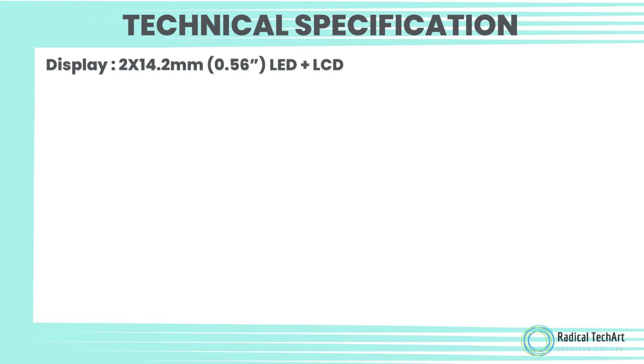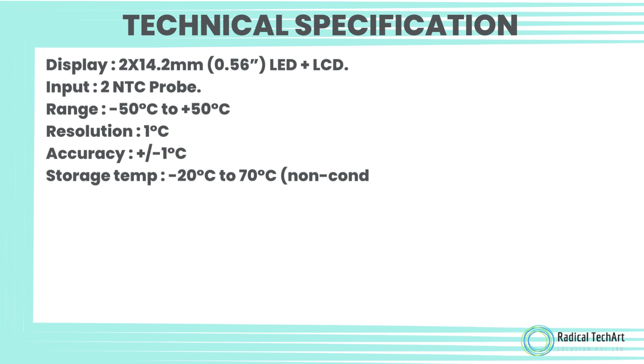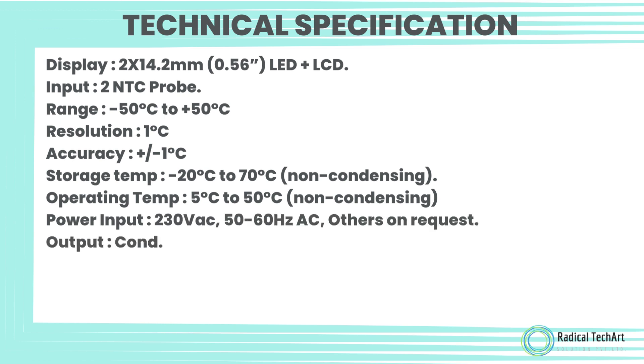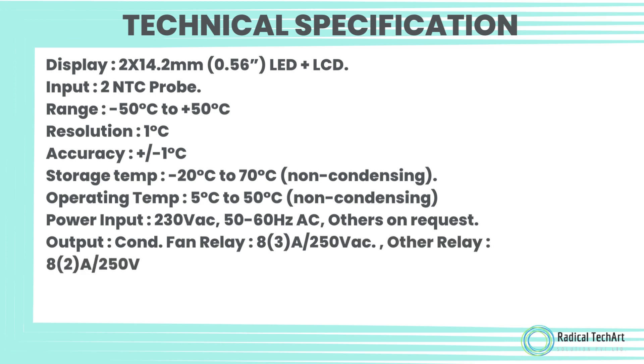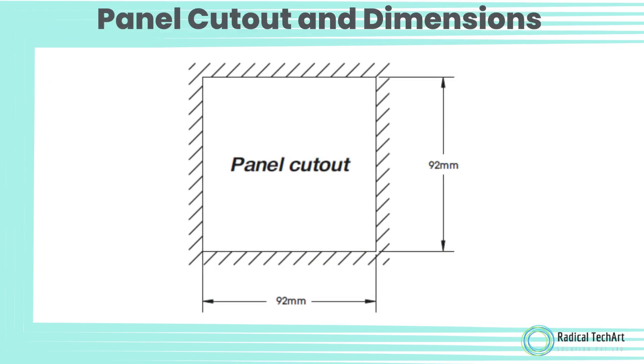Display: 2×14.2mm (0.56 inch) LED plus LCD. Input: NTC probe, range minus 50°C to plus 50°C, resolution 1°C, accuracy ±1°C. Storage temperature: minus 20°C to 70°C non-condensing. Operating temperature: 5°C to 50°C non-condensing. Power input: 230V AC, 50–60Hz. Output: condenser fan relay 8A/250V AC, other relay 8(2)A/250V AC, alarm relay 5A/250V AC. Dimensions: front 96×96mm, depth 85mm, panel cutout 92×92mm.